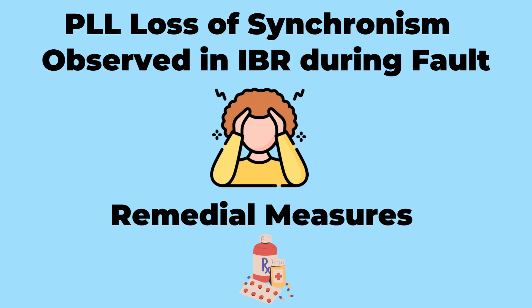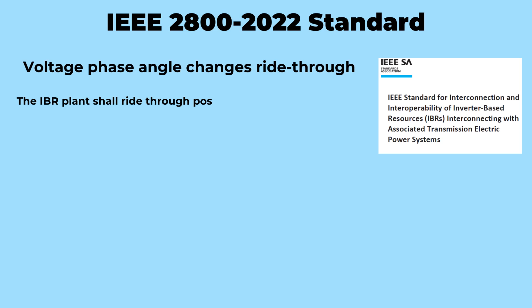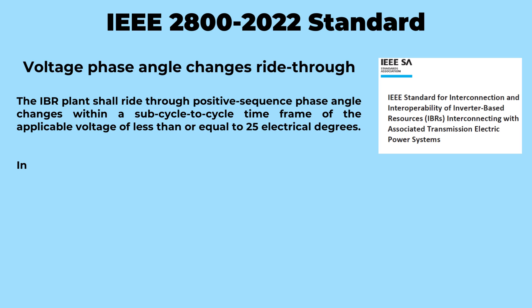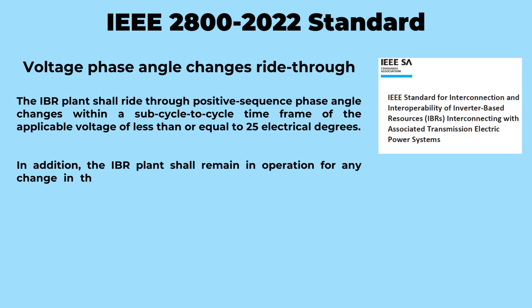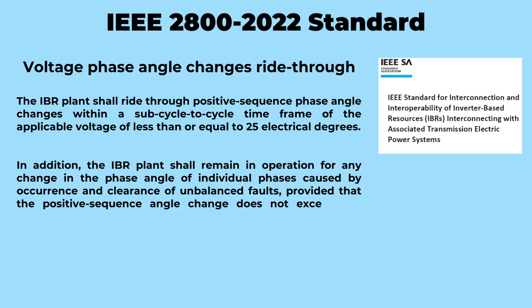Now let us look at what is provided in the IEEE 2800 standard for IBRs. The standard requires IBR plants to have voltage phase angle change ride-through capability. IBR plants should ride through positive sequence phase angle changes, swiftly adapting to voltage fluctuations and seamlessly adjusting to phase angle changes of less than or equal to 25 electrical degrees per sub-cycle. This means that during a fault, if a phase jump of 25 degrees or less is observed, there should be no loss of synchronization, momentary cessation, or inverter tripping on any protection. These criteria are to be defined by the planner and operator through system study.